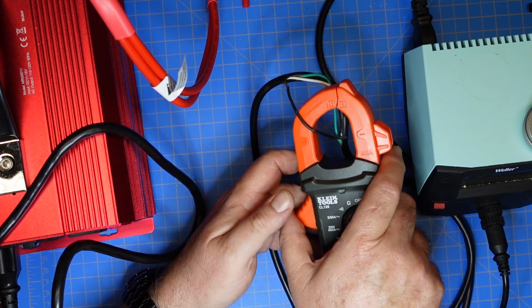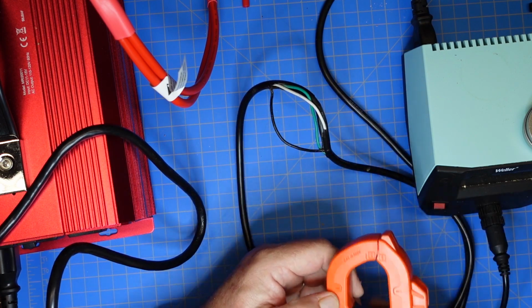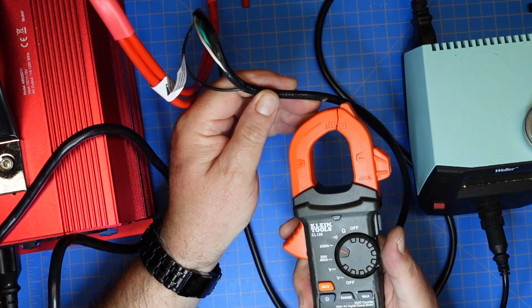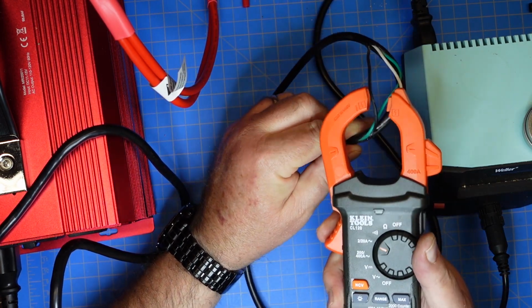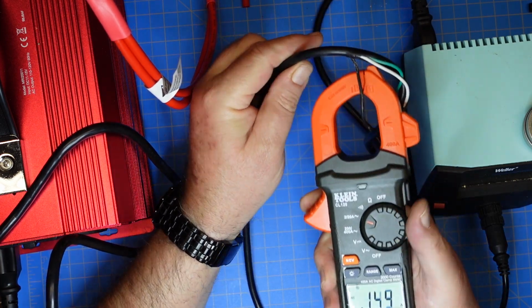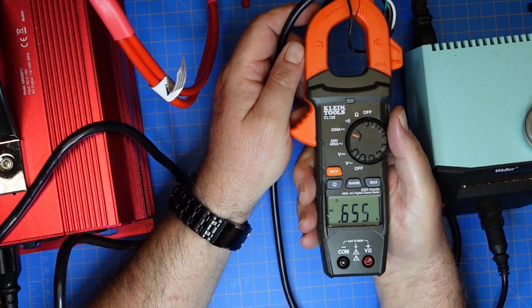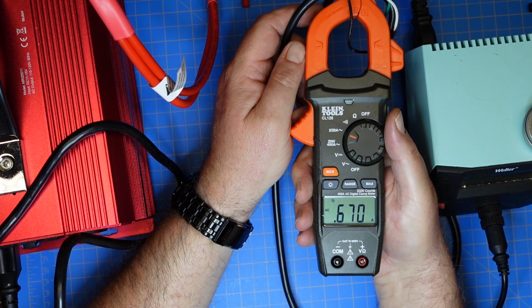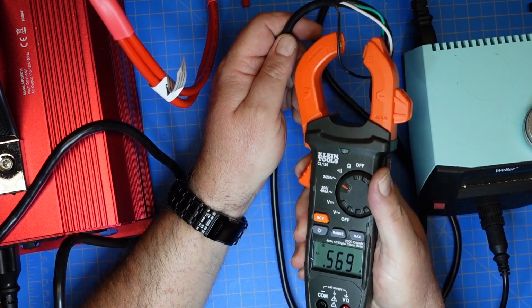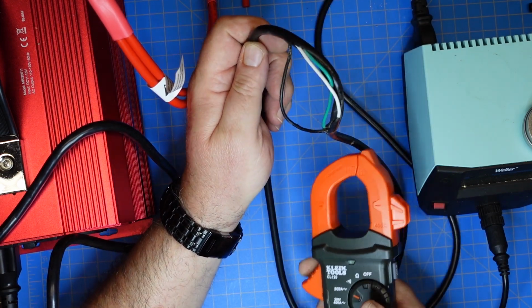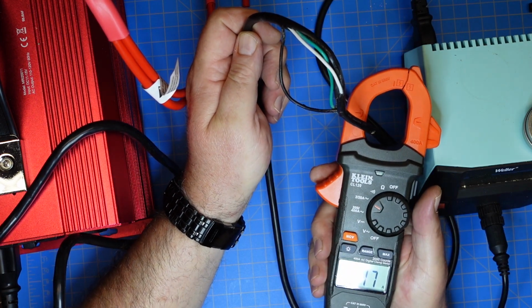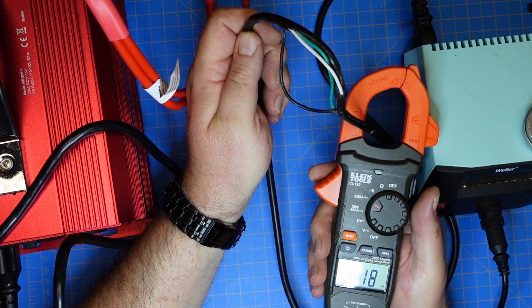But if I test this with the entire cable for this device -- I don't know if I had that on camera, so let me do that again. We're going to test the hot wire there, and you can see we're pulling about 0.7 amps of current. Now, if I test the entire cable, we get almost nothing.